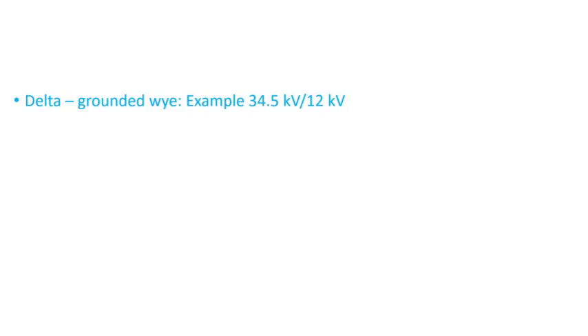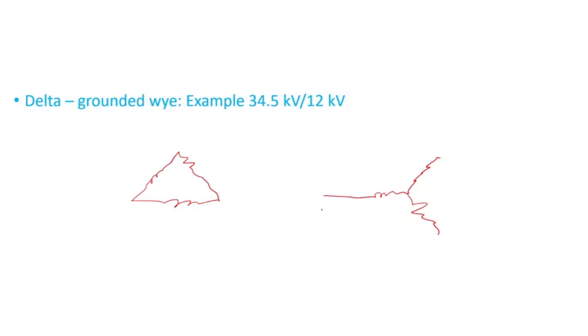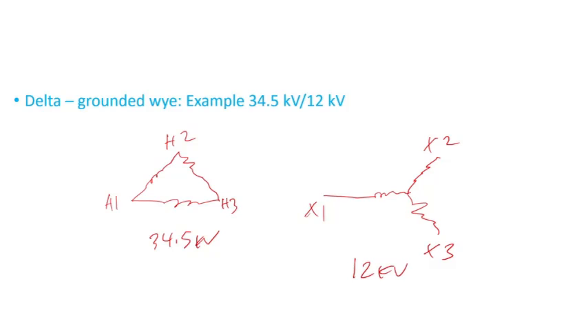For a delta grounded-Y example — say 34.5 kV to 12 kV — and just a disclaimer: I'm not worried about vector group or polarity for this video, the intent is just to look at the test connection. So you have H1, H2, H3 bushings on the 34.5 kV delta side, and X1, X2, X3 bushings on the 12 kV side, with the neutral connected to the X0 bushing and grounded.